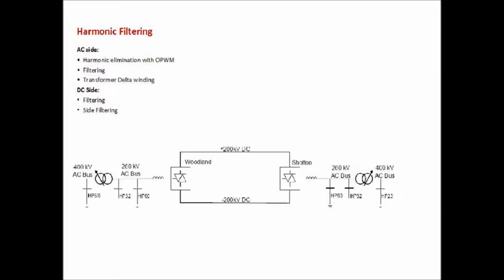Then we're on to what's actually on the system. The first is our own. The east-west interconnector is the first plant to be issued harmonic limits in Ireland in recent times. Basically, it's got filters at AC and DC level. On the AC side, it's got harmonic filters at the 5th, the 8th, the 32nd, and the 60th. And it also has some filtering on the DC side.